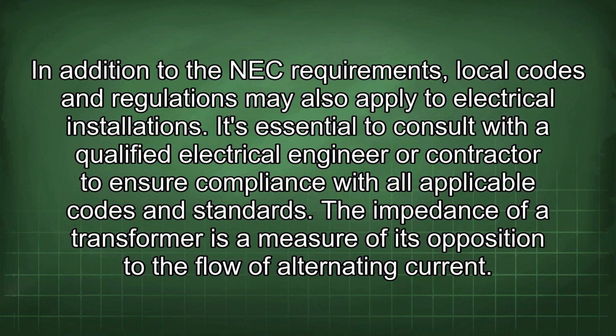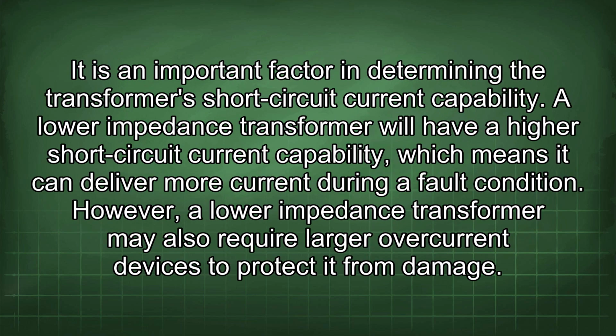In addition to the NEC requirements, local codes and regulations may also apply to electrical installations. It's essential to consult with a qualified electrical engineer or contractor to ensure compliance with all applicable codes and standards. The impedance of a transformer is a measure of its opposition to the flow of alternating current. It is an important factor in determining the transformer's short-circuit current capability. A lower impedance transformer will have a high short-circuit current capability, which means it can deliver more current during a fault condition. However, a lower impedance transformer may also require larger overcurrent devices to protect it from damage.